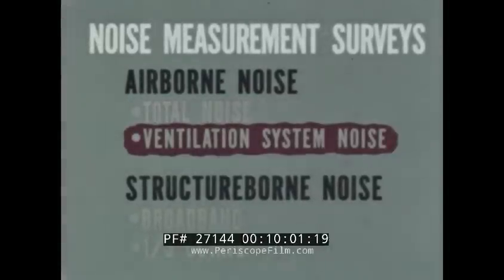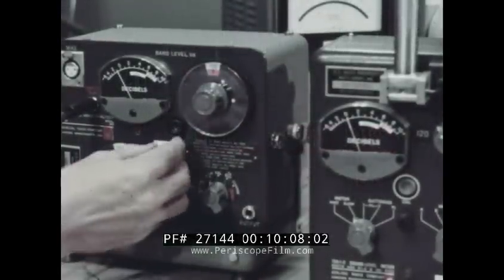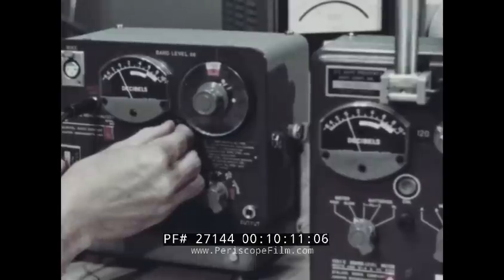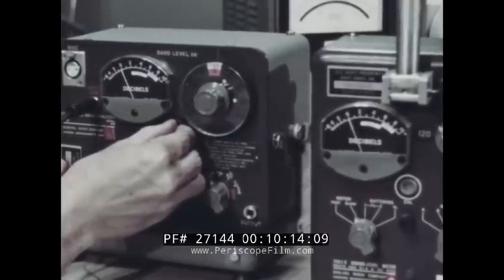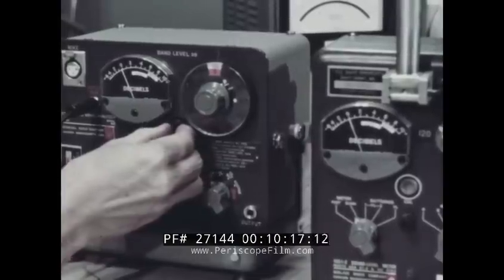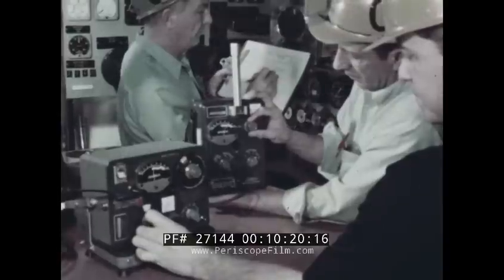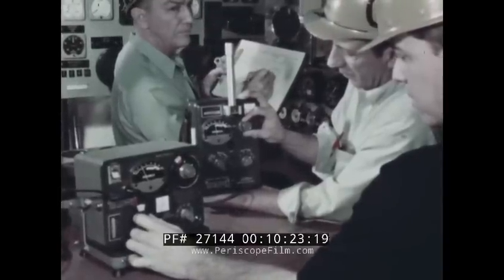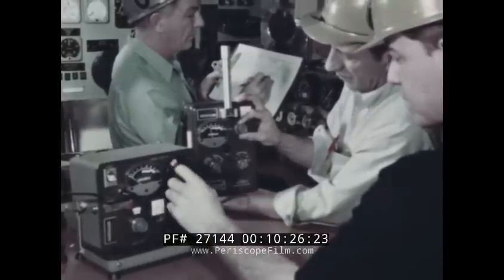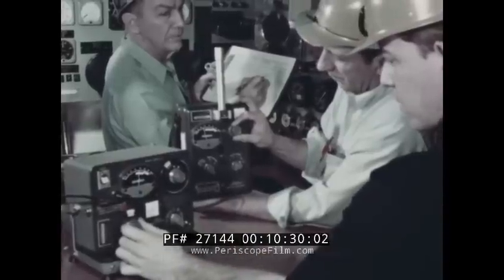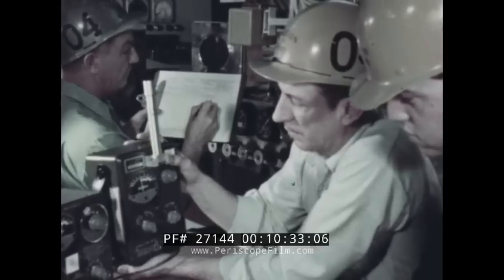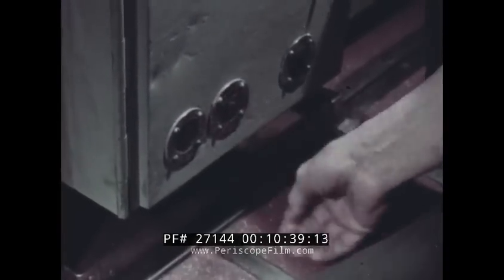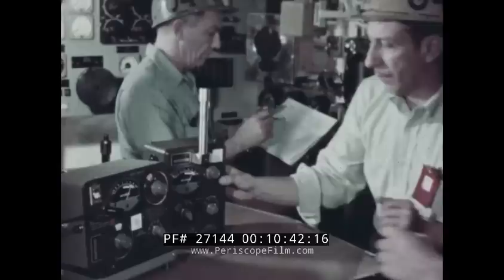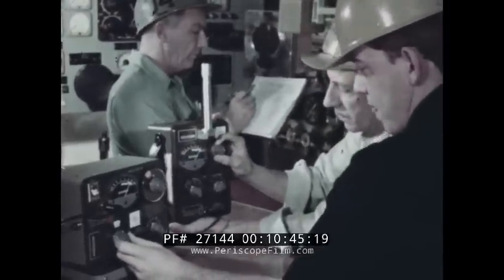For ventilation system noise surveys, the same type of equipment can be used. As you've seen, preparing the gear involves calibrating the sound level meter and then making sure the analyzer gives an identical reading. Aboard ship, you again start with background noise levels. But this time, you're interested in the noise caused by the ventilation or air conditioning system. Turn the system on at high speed. Then take the data readings to determine the maximum noise level from this source.